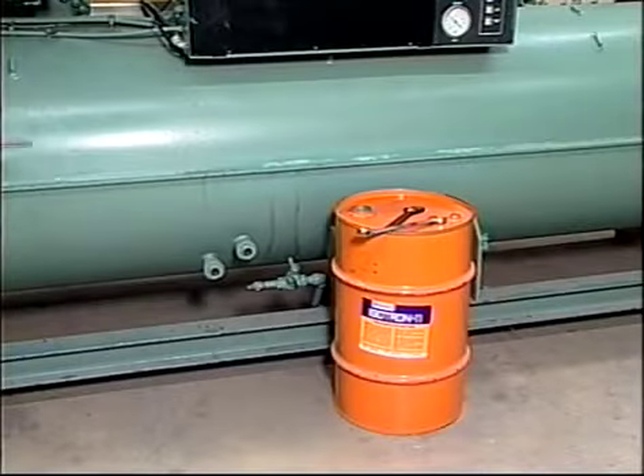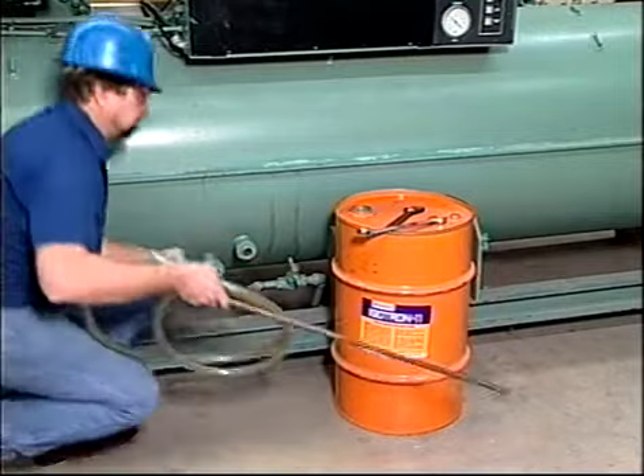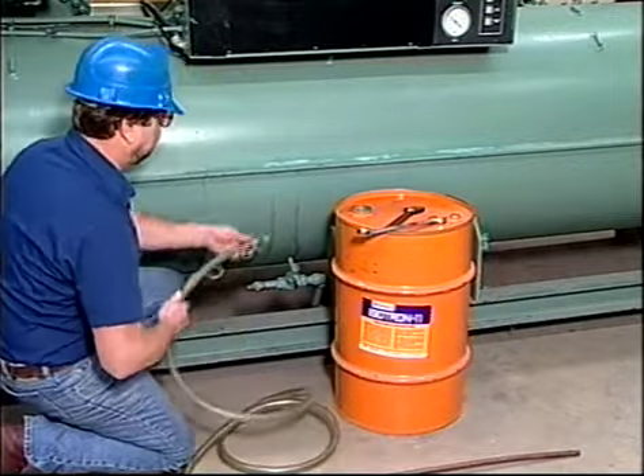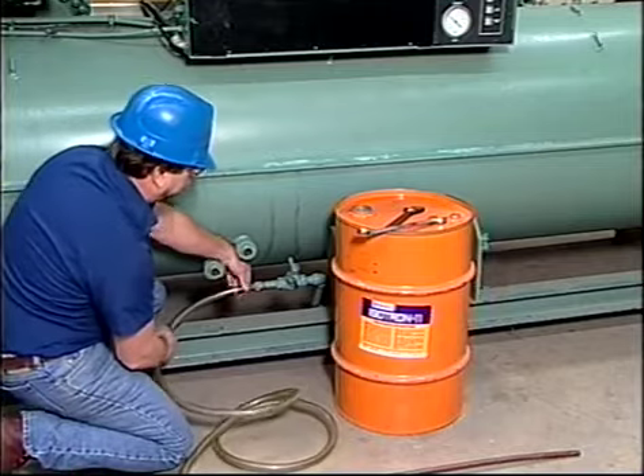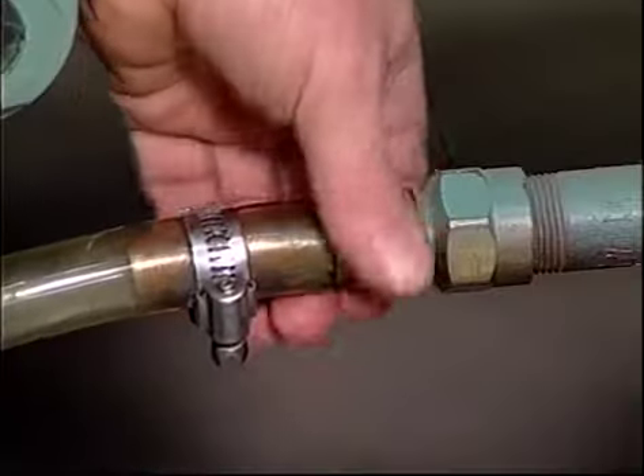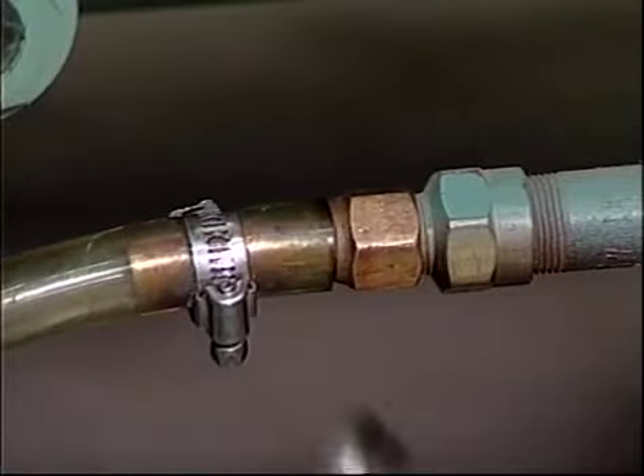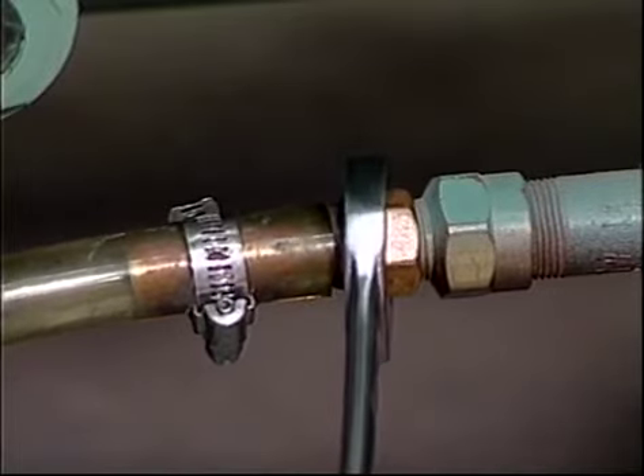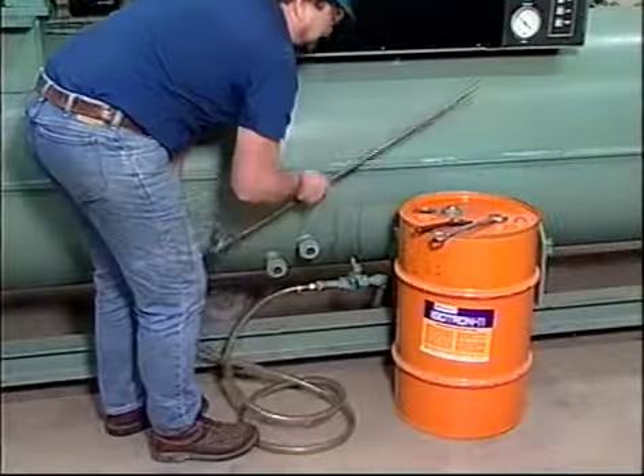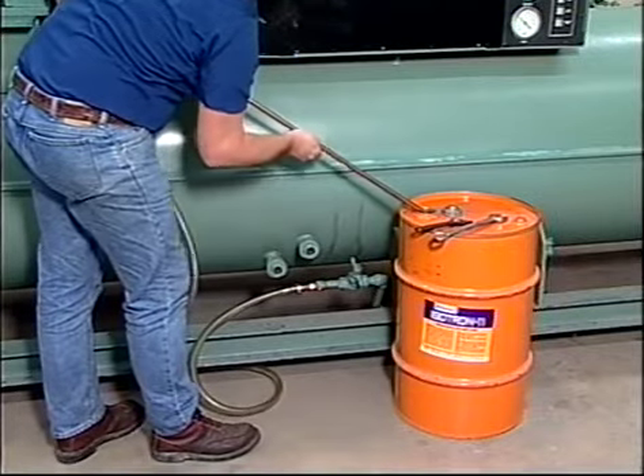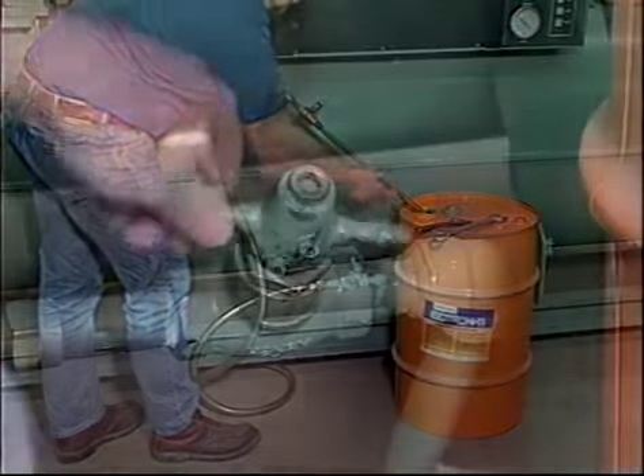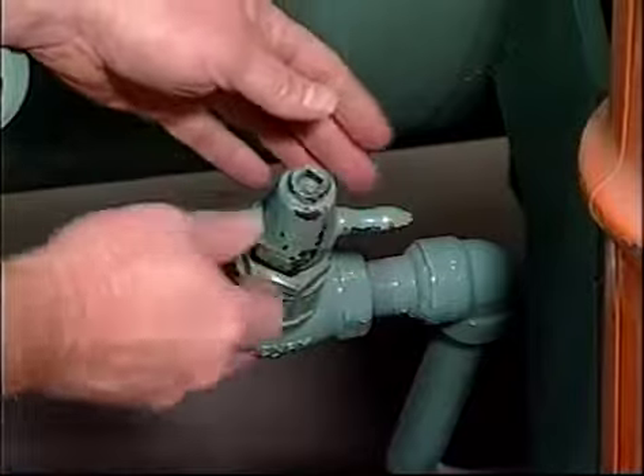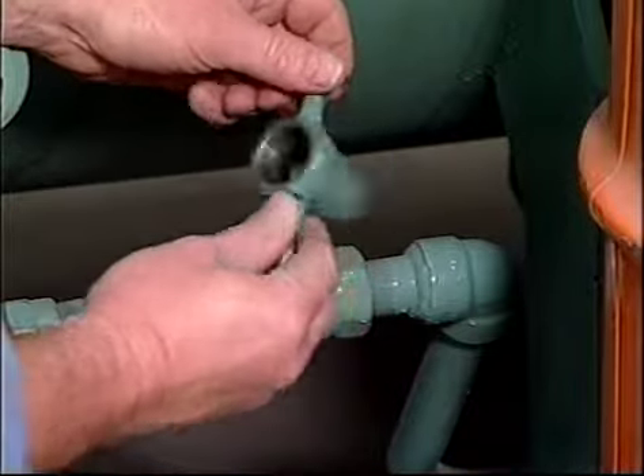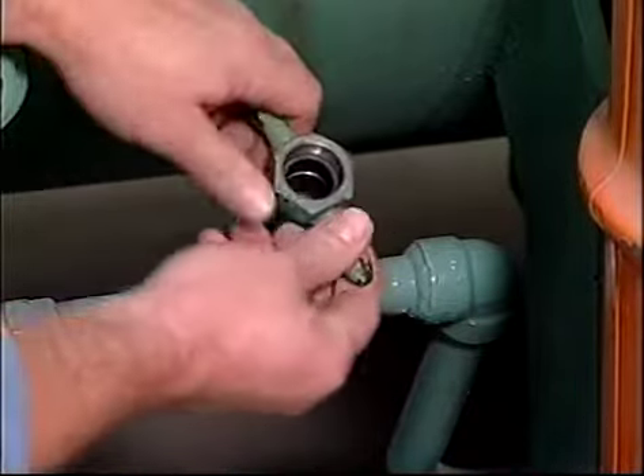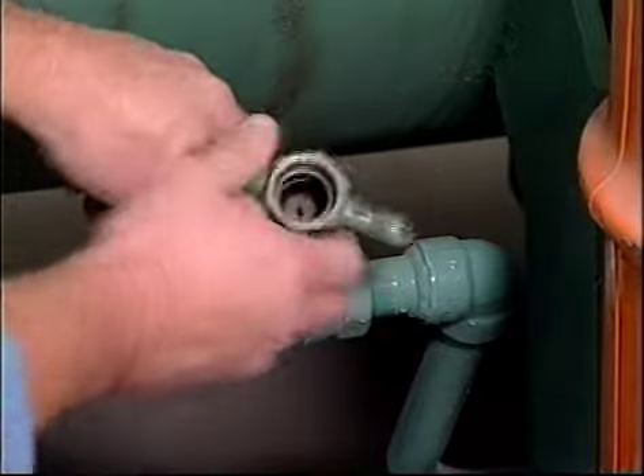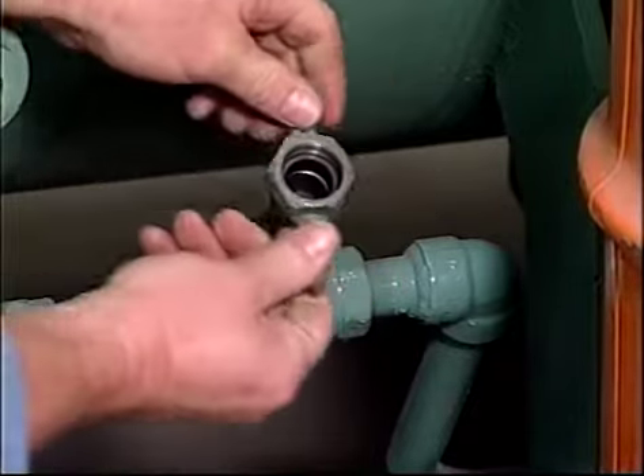Now we come to something that every owner of air conditioning equipment must face: refrigerant management. 10 or 15 years ago, refrigerant management was pretty simple. When you needed to open up a system for maintenance or repair, you stored or blew off the refrigerant, and when you closed up the system, you charged in whatever new refrigerant was needed. If you needed more refrigerant, you sent somebody out to buy it. There was no penalty, except for the refrigerant cost, for leaks, and nobody knew or cared much about ozone depletion.